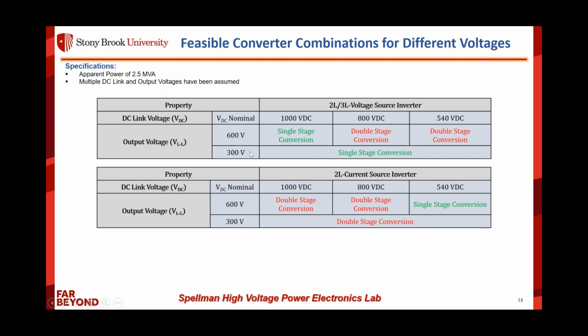However, if I'm moving from 300 volts to 600 volts, I only have the choice of going with a single stage VSI operation, and I only have the choice of going with the 1000 volt DC link. That means you have to double your DC link voltage to make that happen, for this 2.5 MVA calculation example.